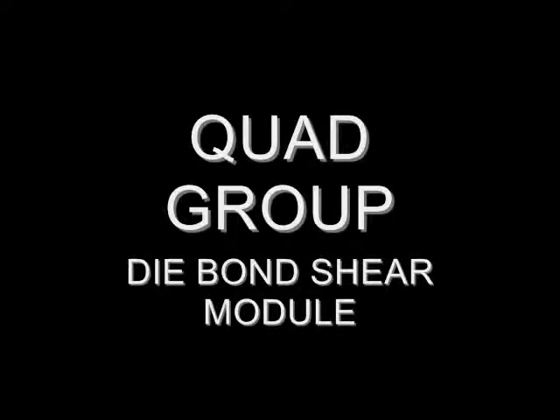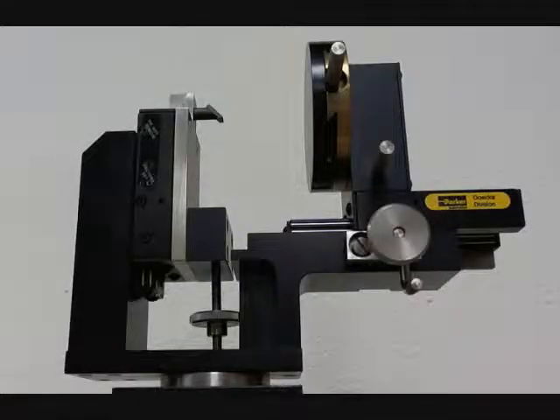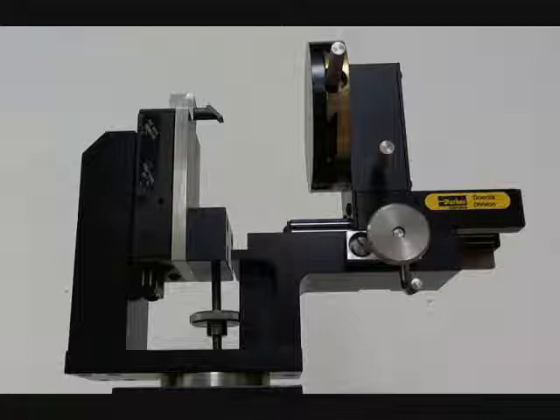The die shear module is an extension of the pull down breaking point platform and is used to determine die bond strength by forcing a shear wedge against the component edge until failure.